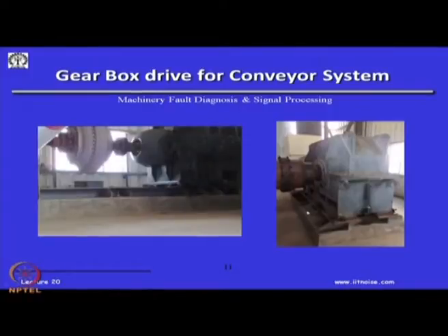Imagine doing such an arrangement 100 meters above the ground, and then how do you ensure that they are all aligned? These are provisions where shims can be used. And to ensure that the vibration levels are less than the levels allowed as per the ISO standard, we have to monitor at all these possible locations, in this case 18 locations into 3, and see what the highest levels are and whether they qualify the vibration standard.